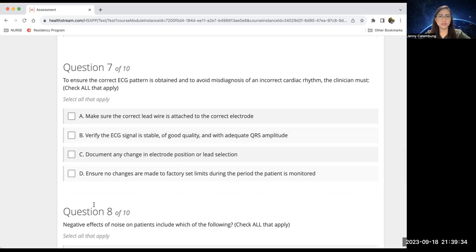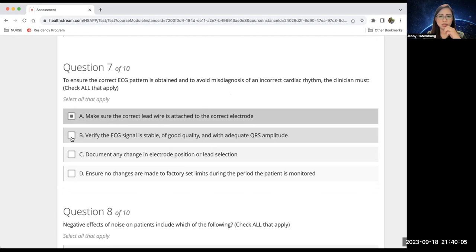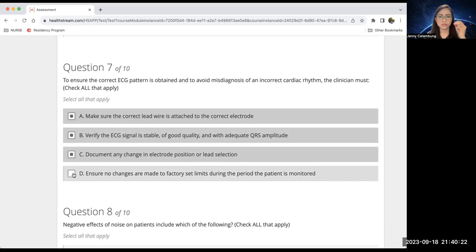To ensure the correct ECG pattern is obtained and to avoid misdiagnosis of an incorrect cardiac rhythm, the clinician must make sure the correct lead wire is attached to the correct electrode. Of course. Measure electrode, verify ECG signal is stable and of good quality. To avoid misdiagnosis, document change in electrode position or lead selection. Okay, ensure no changes are made to factory set limits during the period the patient is monitored. I don't know.